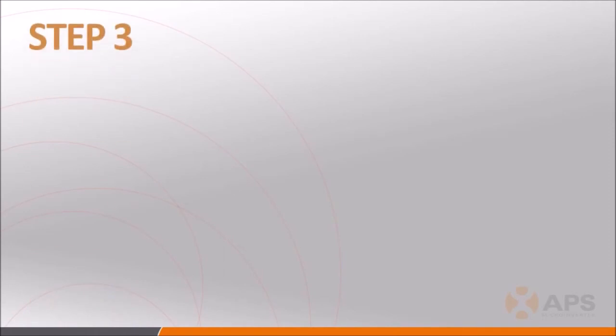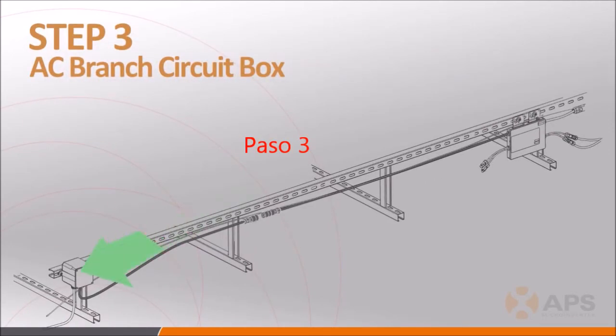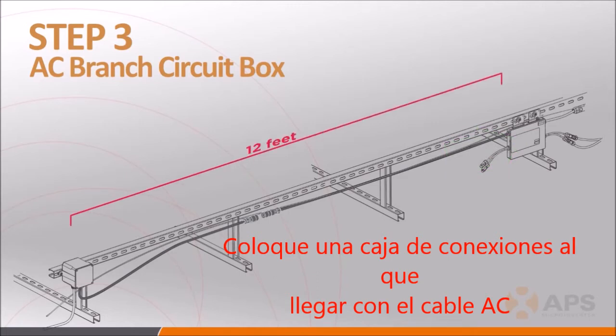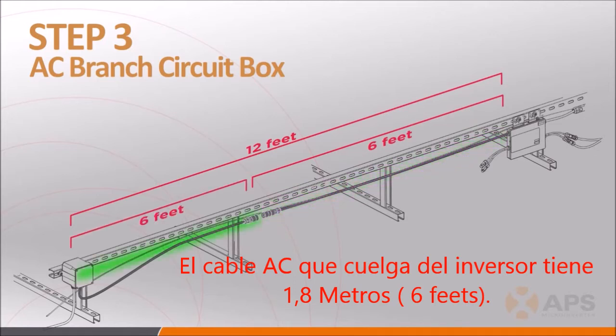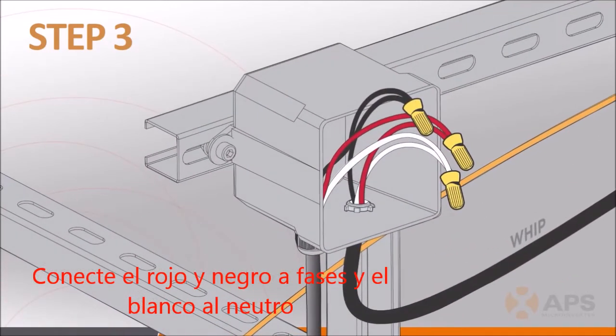Step 3 involves installing the AC branch circuit junction box in a suitable location, as close to the end of a branch of modules as possible. You'll have approximately 12 feet of AC cable to work with — 6 feet of cable associated with the last inverter in the branch and 6 feet of AC connector cable, sometimes called a WHIP. Make sure to wire the conductors correctly: L1 is red, L2 is black, and neutral is white.